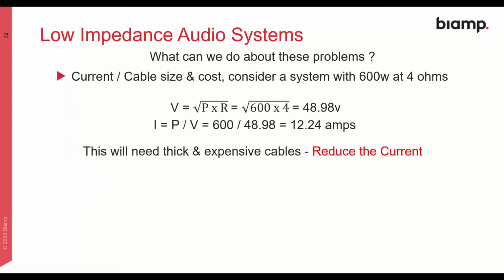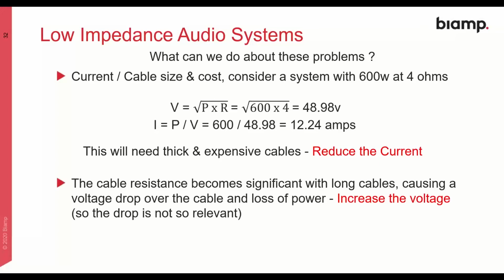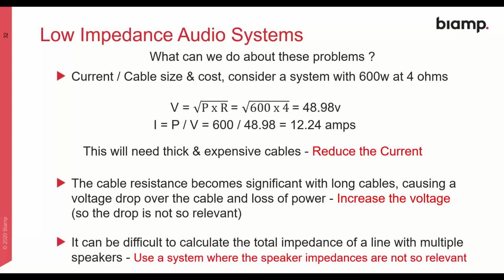So what can we do about this? Firstly, in this case, the current and the cable size and cost, we can try and reduce the current. Okay, that's easy to say, but how do we do that? Secondly, the resistance becomes significant with long cables, and this causes the volts to drop down the cable. So one way around this is to increase the voltage, and this means that the volts drop is not so relevant in the grand scheme of things.